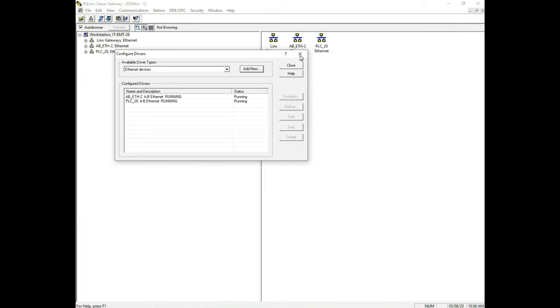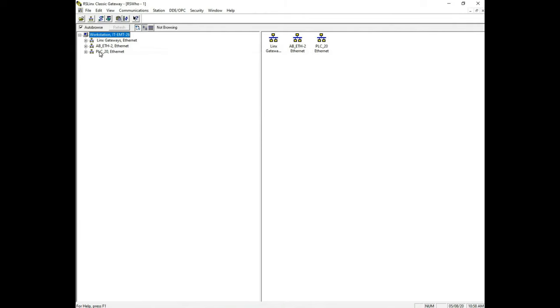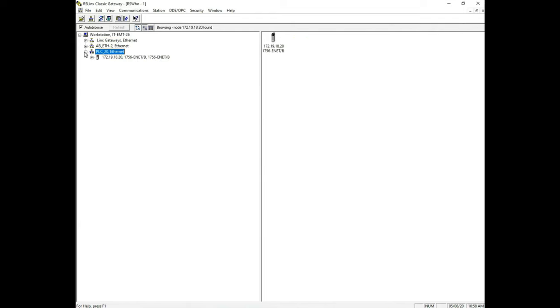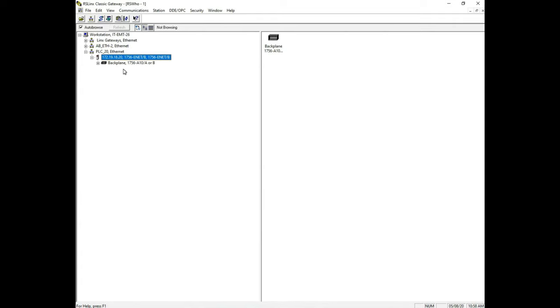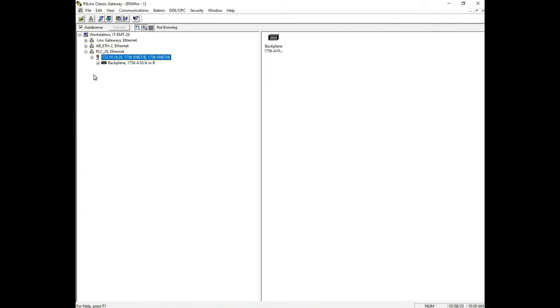Let's close this out and see what happened. Notice over here now we see our PLC 20 Ethernet. If I expand this, the first thing that's going to happen is we're communicating from our computer to our Ethernet card. That's the first thing that happens because it's connected to our network. The next thing that the Ethernet card is connected to is our back plane, and so that's the next thing we see. Now connected to the back plane is all the rest of our PLC cards, and so now when we look over here we see our PLC rack here.